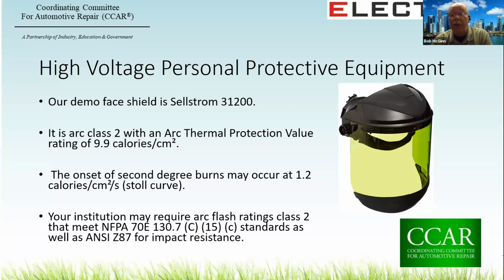It is a Sellstrom 31200. The reason I bring it up specifically is that it is the only arc flash 2 rated protection we could find that isn't connected to a hard hat. Why? Because most PPE for electric is designed for linemen working out on high voltage wiring. They haven't caught up to the automotive sector yet. Now, as arc class 2, this has an arc thermal protection value rating of 9.9 calories per square centimeter. The ATPV rating is protection against incident heat or arc flash, not necessarily electrical isolation.